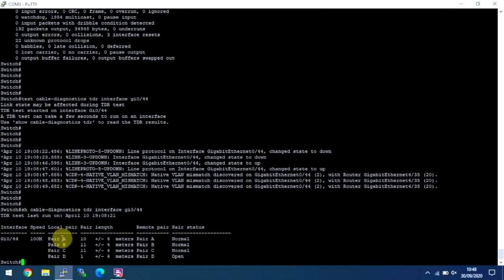So it took a little while to get there, but now we can actually see that at roughly pair D, roughly one metre. So this is a 568B cable, so you'll have orange, white, orange, green, white, blue, white, blue, green, and this is your brown, white, brown, pair D. And that is exactly what James has cut.